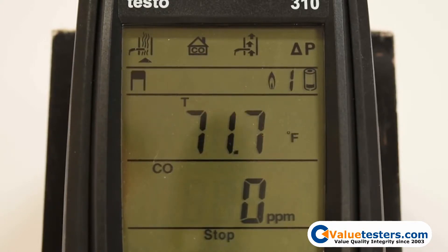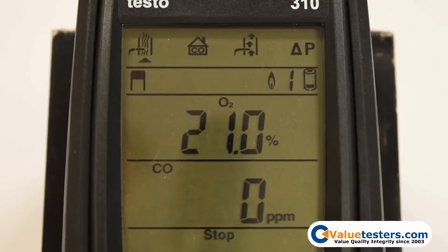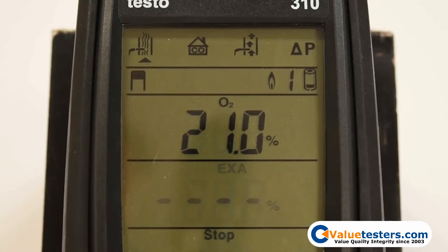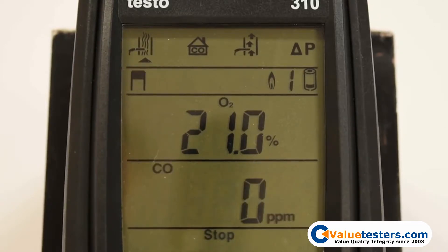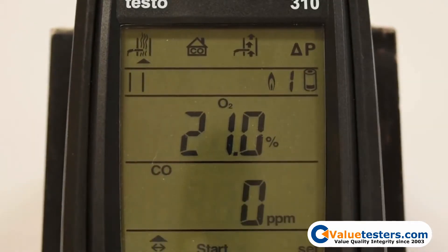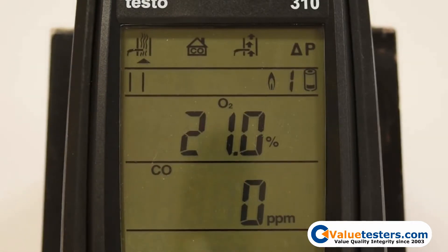The up arrow will scroll through the top line's measurements, and the down arrow will scroll through the bottom line's measurements. When you are satisfied with your readings, you can send your measurements to the optional Testo IR printer by pressing the Print button.